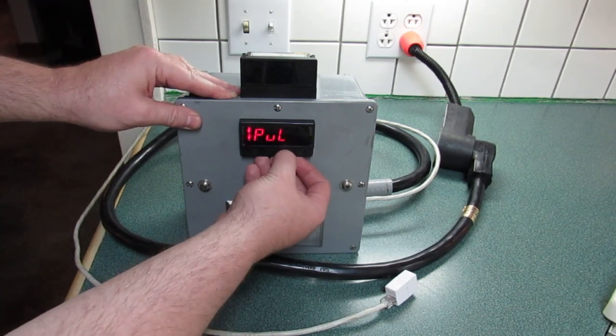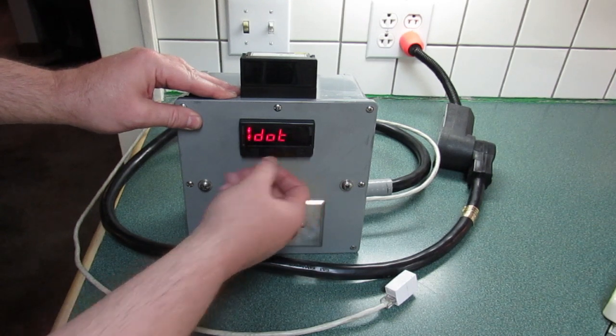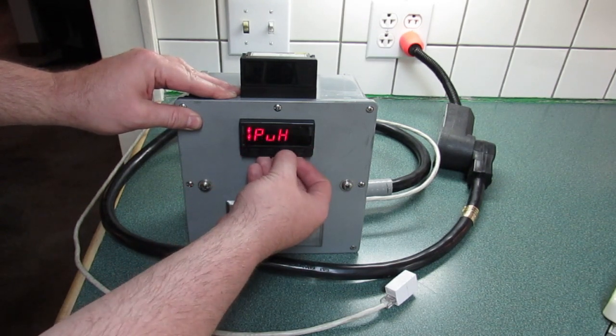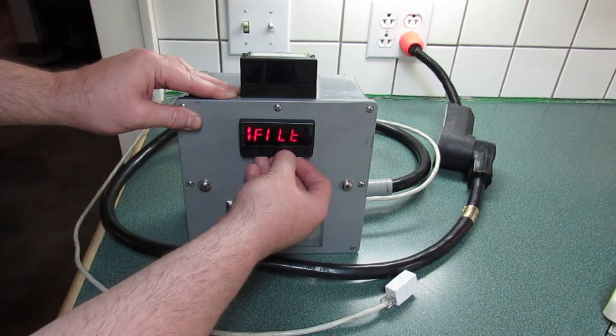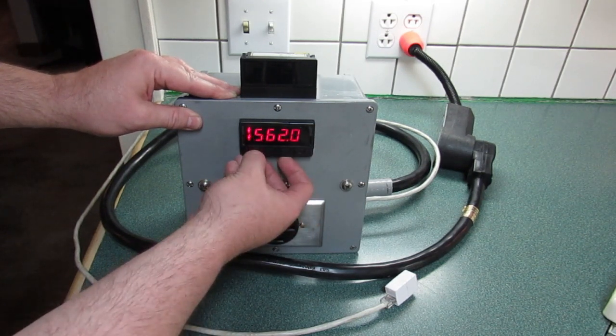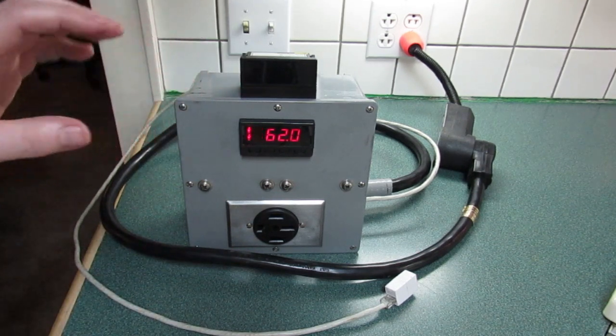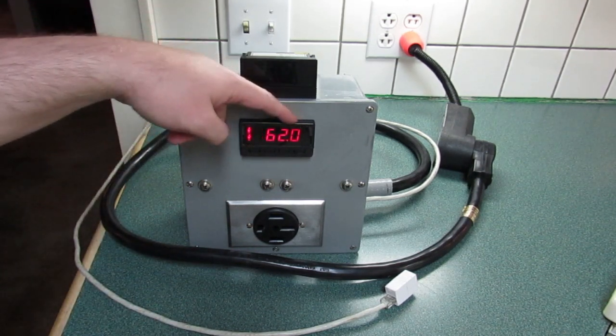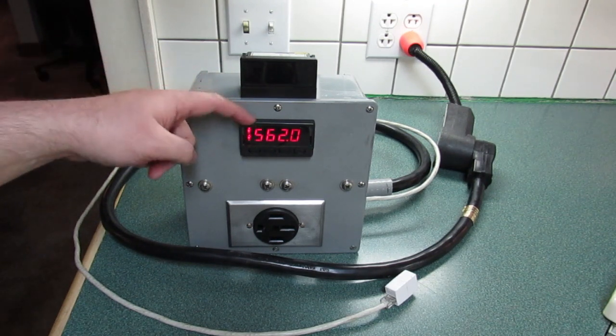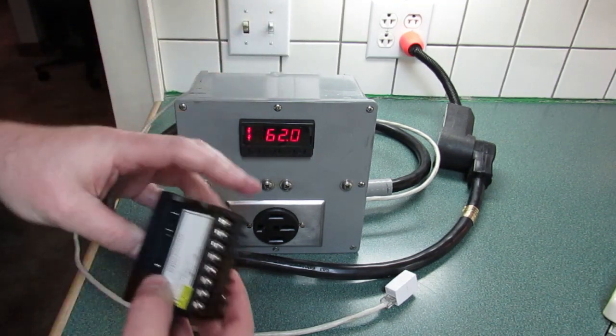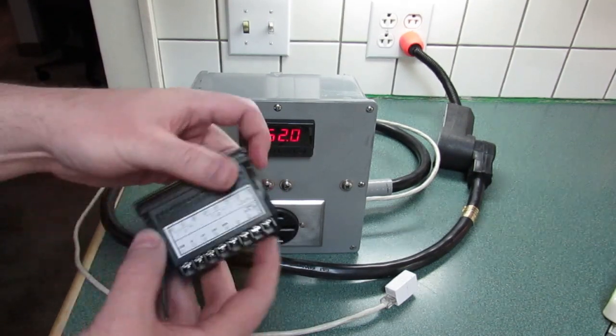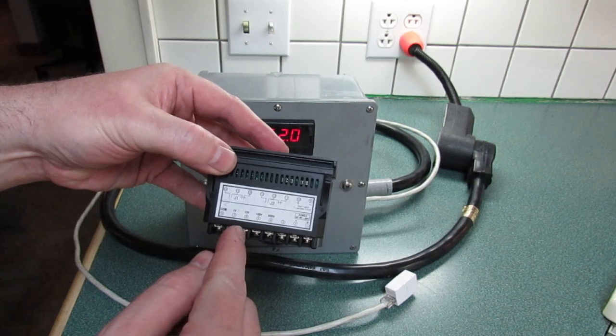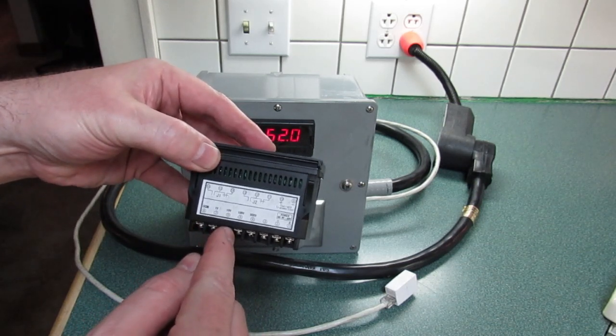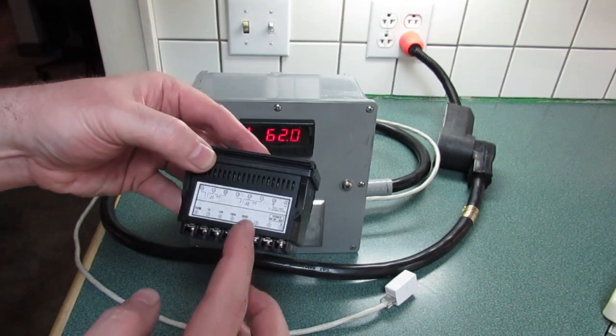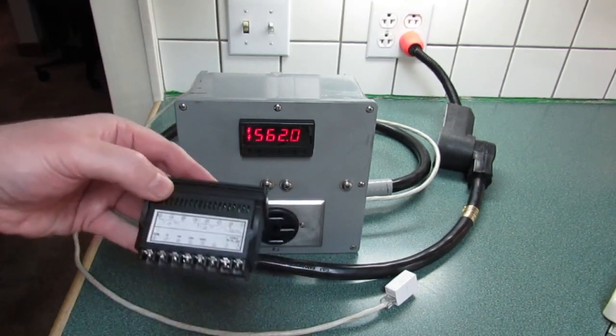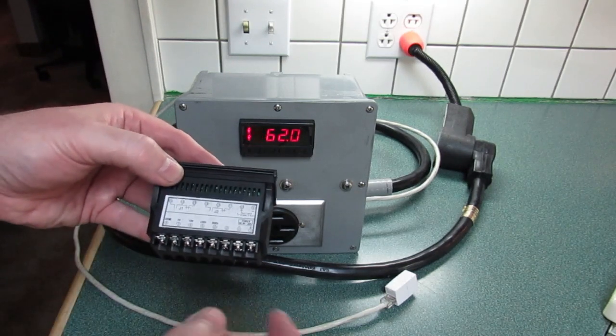So the PUH and PUL settings: the dot is just the number of decimal places shown on the meter. The H and L determine a kind of scaling factor. This meter can read up to 500 volts, and it's got a 500 volt connection as one of the terminals. Depending on which one you hook this up to, you either have roughly 1 volt, 10 volts, 100 volts, or 500. So if you're on the 500 lead, it has a bigger range of 0 to 500.